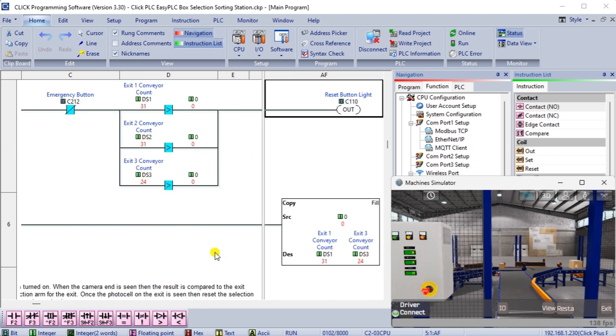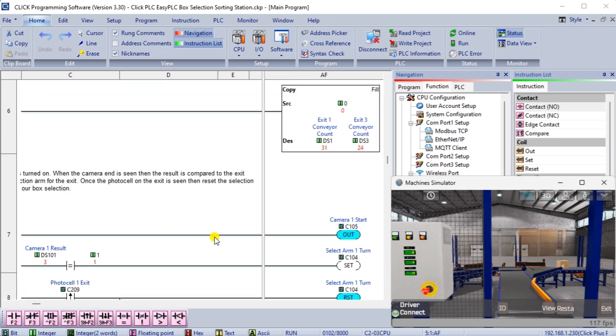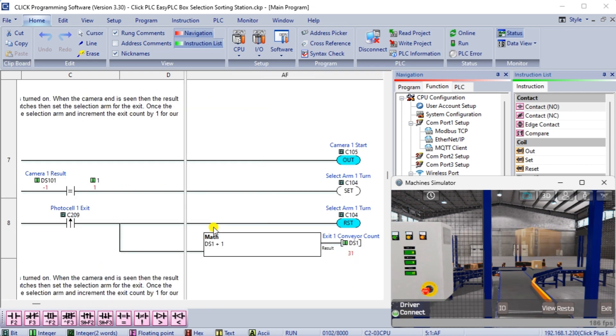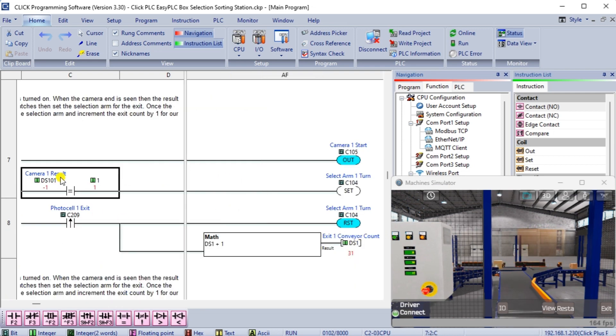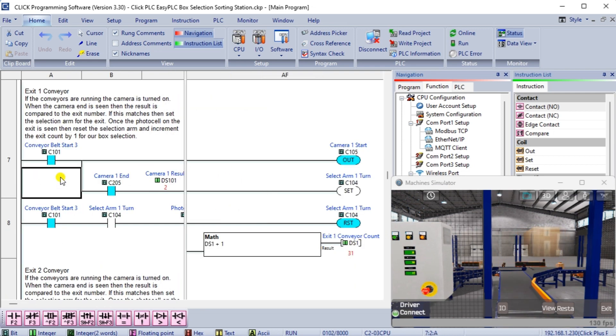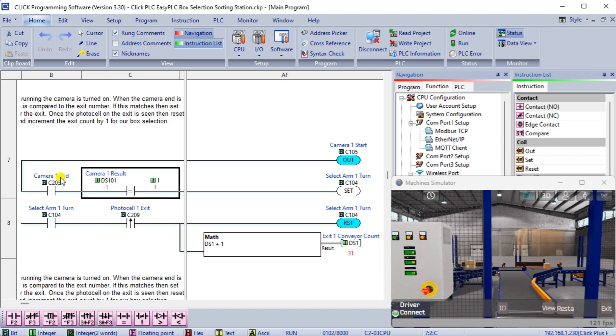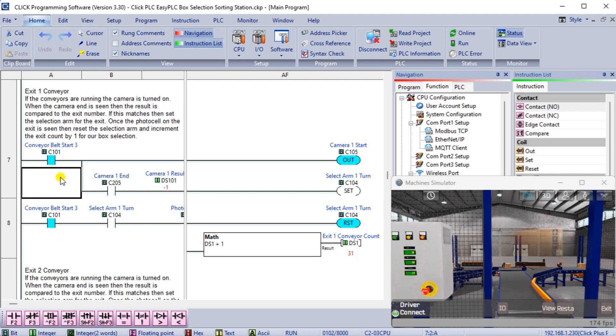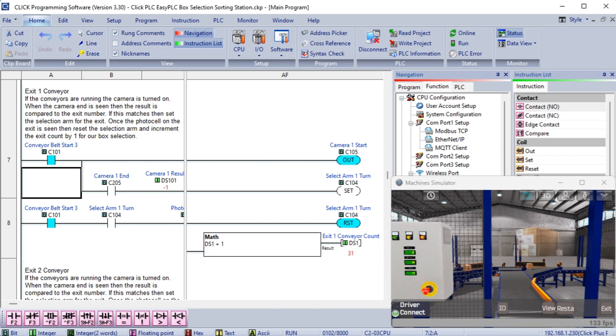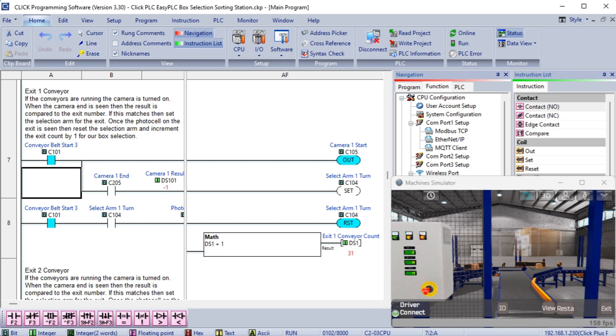Exit 1 conveyor. If the conveyors are running and the camera is turned on, the result is compared to the exit number when the camera end is seen. If this matches, then set the selection arm for the exit. Once the photo cell on the exit is seen, reset the arm selection and increment the exit count by one for our box selection.